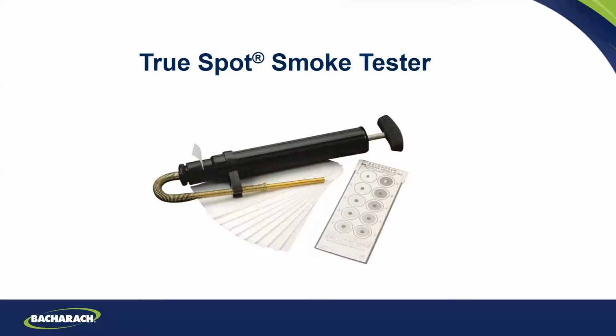1/16th of an inch of soot will lower your efficiency 8%. So before you take a smoke test, we invented the True Spot smoke tester back in 1947 in conjunction with Shell Oil. It looks like a bicycle pump here - you pull this probe out, put it in a stack, and put in a piece of chemically treated paper. You can't use a bar napkin, you have to use our chemically treated paper. You pump this 10 times.